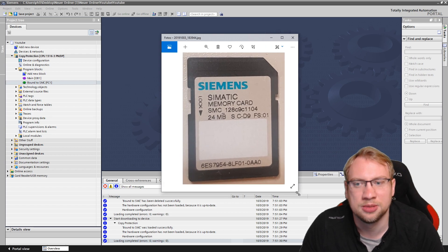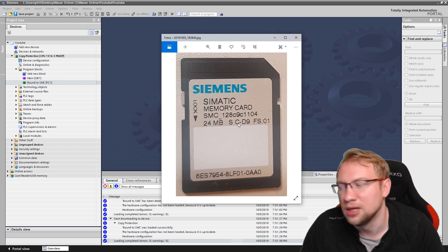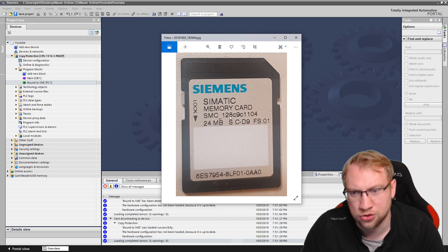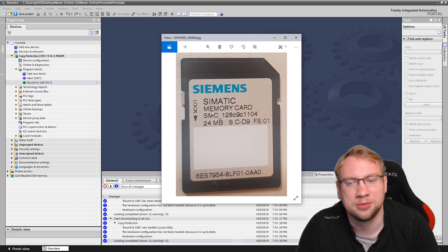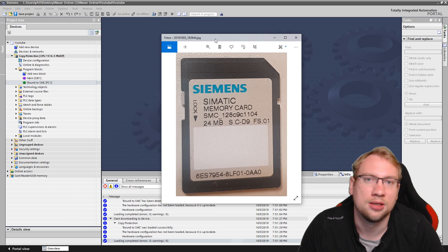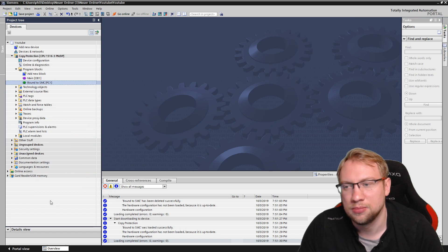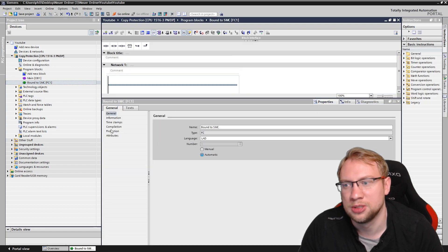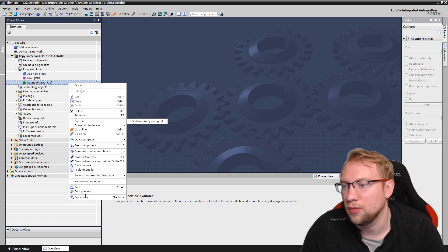We want to only download and run this program on one specific memory card. The SMC — Siemens Memory Cards — look like this. Every SMC has a code written on it; this one is SMC_128, code C9C1104. This is the memory card I'm using in this PLC, and this is what I would have to type in for the protection. I can right-click on the block and select Properties, then go to Protection.